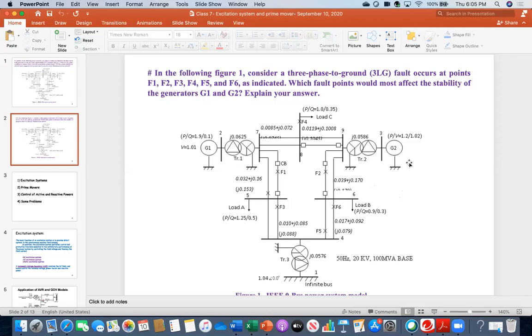If you simulate this system in a software and plot the voltage profile corresponding to each fault point, you'll notice that when the fault is here, this generator's voltage drops much more than at other points. Similarly, when the fault is at F1, since it's closest to this generator, voltage will drop much further, and frequency and speed will rise much higher than at any other point. So as distance increases, there is less impact.